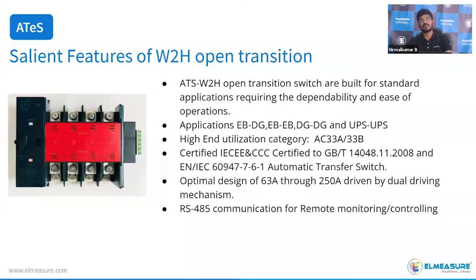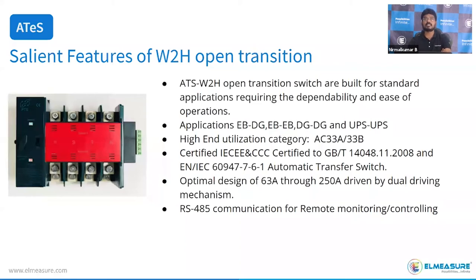Salient features of the W2H: it is a very economical, compact two-position ATS, majorly used for EB-to-DG changeover applications, suitable for generator OEMs and apartment applications. The utilization category for all solenoid ATS is AC33B — usable for any type of load and designed for high inrush current. The product is certified with IECEE and CCC certificate as per IEC standard 60947-6-1, optimal for 63A to 250A ranges, with RS-485 communication in the controller for remote control and monitoring.